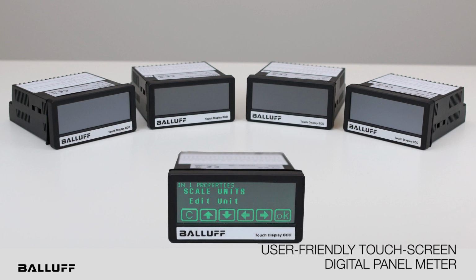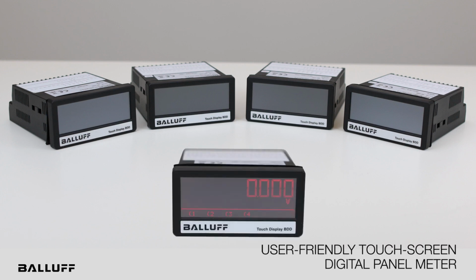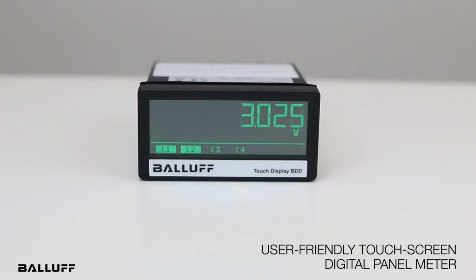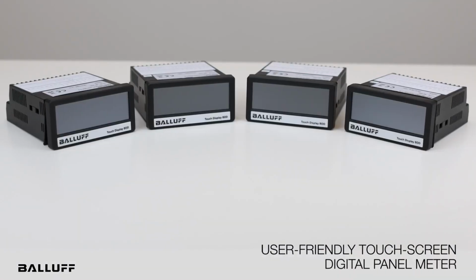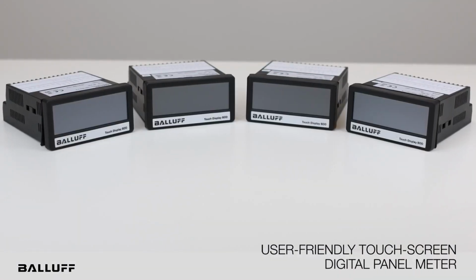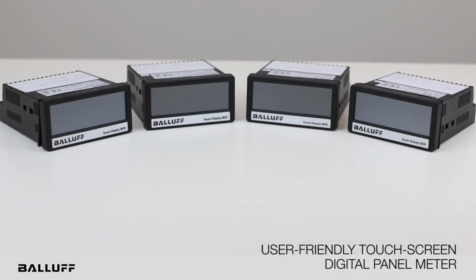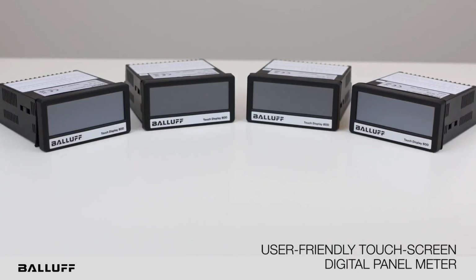The display can be set to different brightness levels in different colors: red, yellow, and green. Versions with switching outputs can offer operator alerts by changing color in response to programmed events. The change in color, for example, from green to red, can grab the operator's attention instantly. Some of the interfacing functionality offered on these panel meters includes a serial communication interface, control inputs, control outputs, and analog signal retransmission.